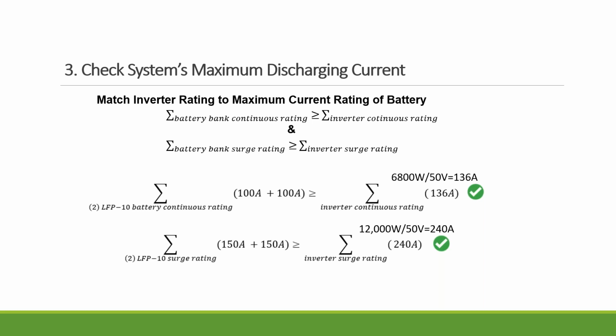And the inverter, the 6848 inverter, has a continuous discharging amperage of 136 amps. So you're good to go. That means the two battery bank will allow the inverter to draw the maximum amperage at 136 amps. And we also check the surge capacity, right?